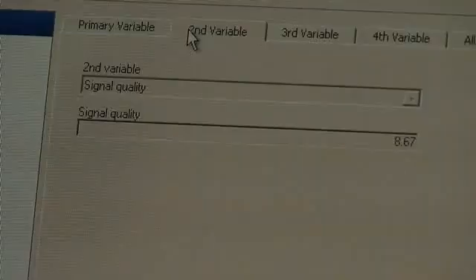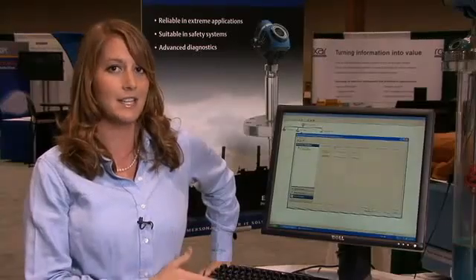In this situation we have a signal quality of 8.67 so it's pretty good, but if the contamination continues to build up then it could cause the signal quality to lower and it'll give an indication of when the probe needs to be cleaned.